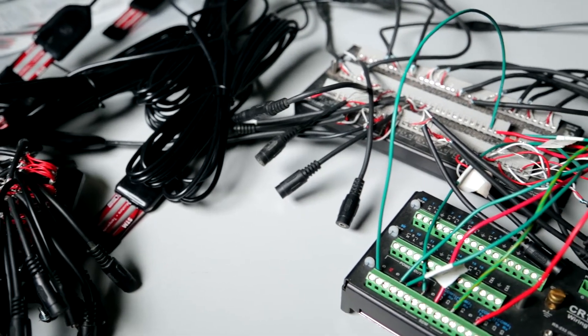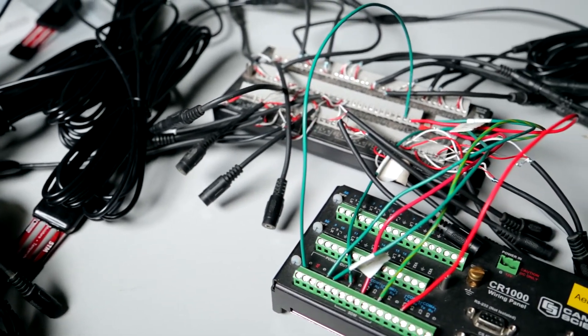Let's move on to the next scenario: SDI-12. You love it, you hate it — it does a lot for you, but it's not perfect and you know it. You've got 32 sensors connected to a common data line, reading them all in SDI-12. You fire up the system and none of them give you any data.